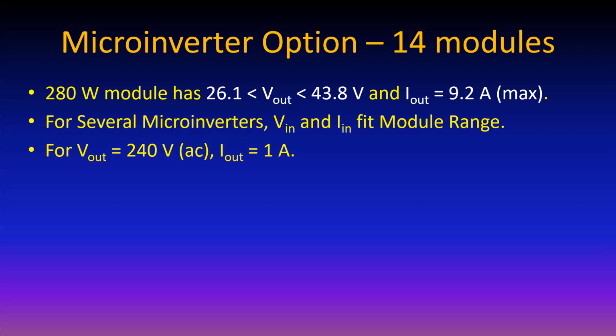For a 240 volt output, the current is going to be 1 amp, okay? And the idea is that 240 times 1 is 240 watts. So that means it acknowledges that this 280 watt module is highly unlikely to ever be running at 280 watts. More than likely, it'll be at 240 or less. And as long as it's at 240 or less, this microinverter is fine. Your annual performance is going to be fine, no problem.